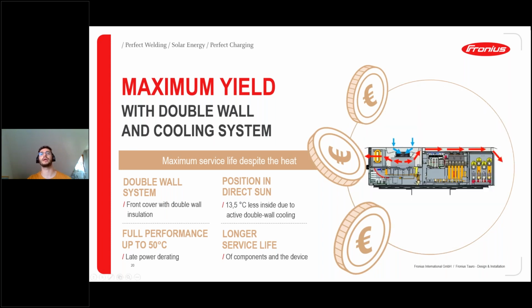Here again we have a cross-cut through the whole inverter, and we can see the actively cooled system. It's sucking in the cold air from the front with one or two fans, depending on how many power stacks you have inside. The hot air is then distributed across the inverter and through this double wall concept, where it gets rid of the heat. So this is how the concept works.